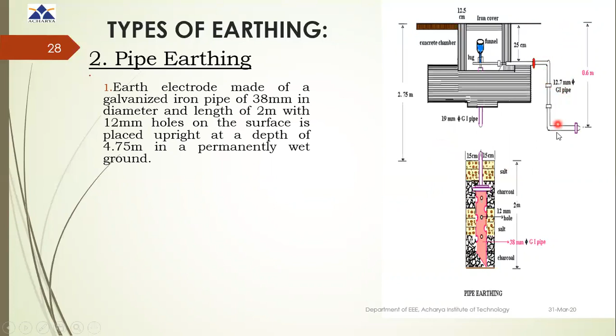This GI pipe of 12.7 mm is placed at a depth of about 60 centimeters, or 0.6 meters, below the surface of the ground. In order to keep the value of earth resistance at a desired level, the area 15 centimeters surrounding the GI pipe is filled with a mixture of salt and charcoal to keep the soil resistance very low.